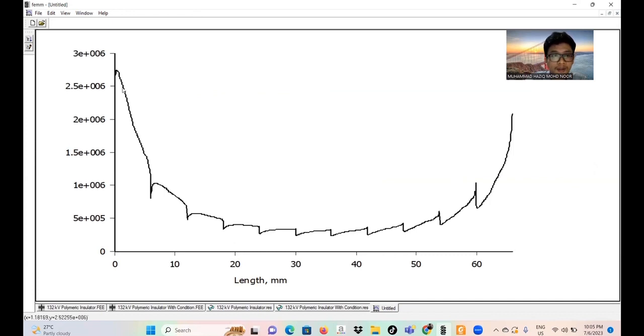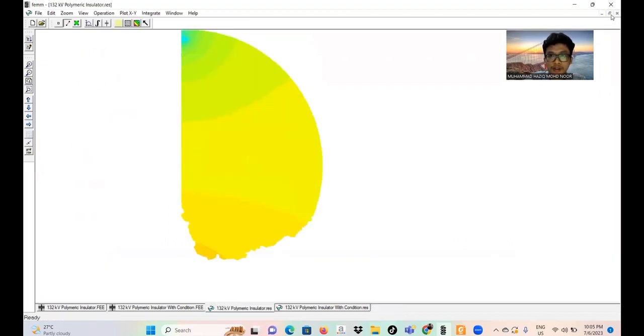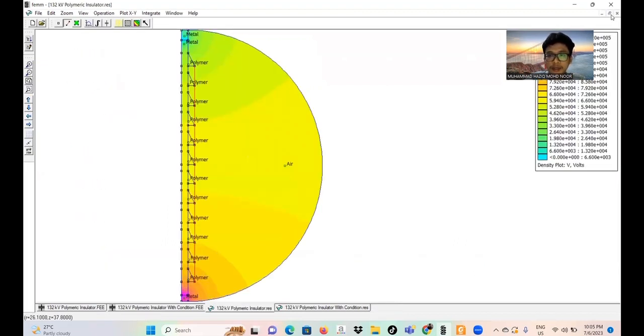that indicates when we measure the E field for dry condition at the creepage of the alternate shade of the polymeric insulator. So we can see it is over 2.6 megavolt per meter, and it will be U shape until it reaches 60 millimeter insulator length. So let's move to the wet condition electrical stress analysis.